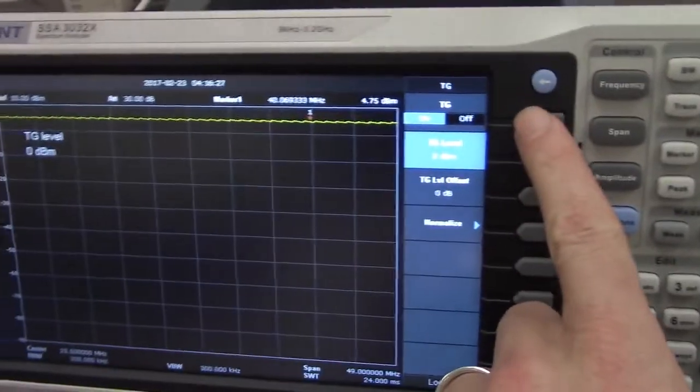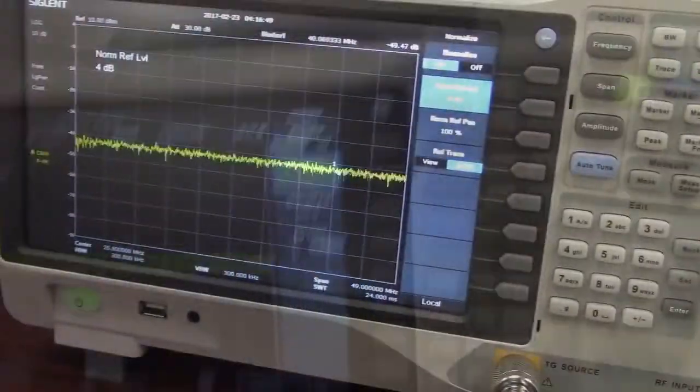Okay, now we're back. I have put the barrel adapter in and now I'm going to turn on the tracking generator. So we've got the tracking generator on. And now I'm going to press normalize and turn the normalize trace on. And now you'll see that the line has gone flat and we are at 0 dB. And now I can take out the barrel. Just take a second, try to do that one-handed.